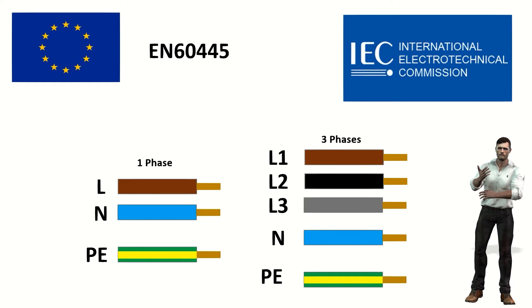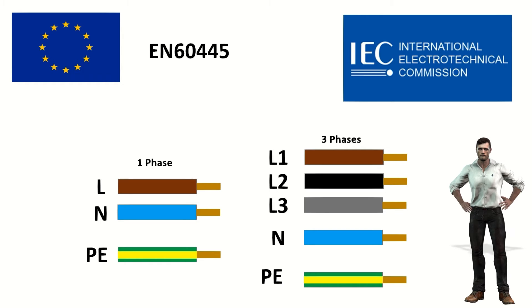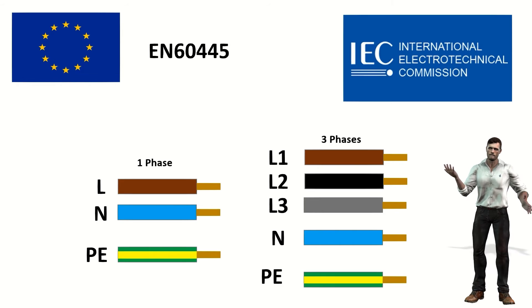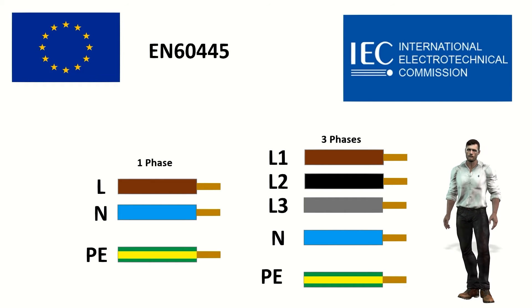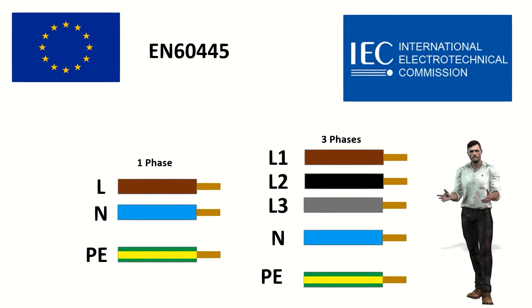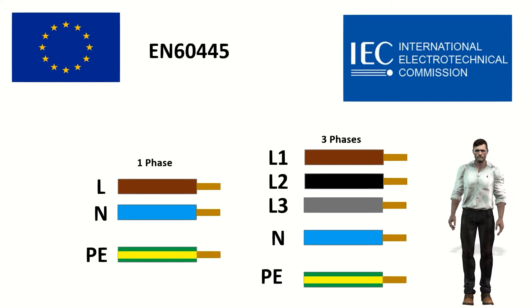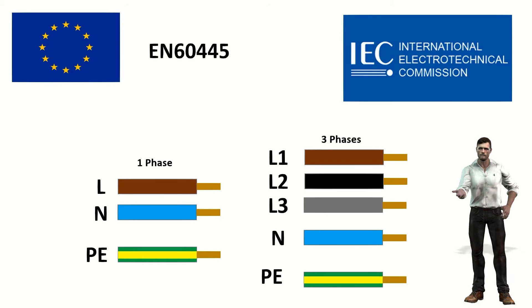In Europe, a large majority of countries apply the EN 60445 standard. For single-phase AC voltage installations, brown is normally used for the phase conductor (L), and light blue for the neutral (N). For the earth or protective conductor (PE), green with a yellow line is used. For a three-phase installation: brown for phase 1 (L1), black for phase 2 (L2), gray for phase 3 (L3), light blue for the neutral (N), and green with a yellow line for the ground or protective conductor (PE).